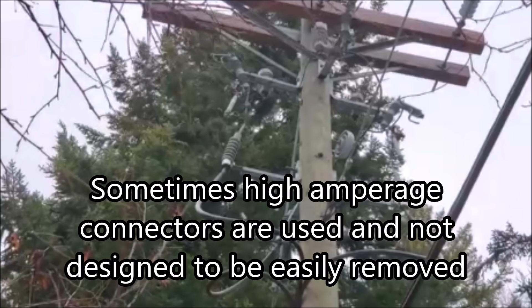So what I'm going to be doing as a precaution, I'm actually just going to take out the whole line. There's some switches I can reach with my truck down the road. So we're going to open the line so that all this three-phase power will be dead. We're still going to ground it on the cables itself. I've seen sometimes guys would suggest to close in the cutout door and install the ground up on the three-phase, as that would make things a little easier, especially off of hooks. But you don't want to install your grounds through a fuse. If I put some solid doors in there, that would be acceptable, but still better off to go right on the cable itself.